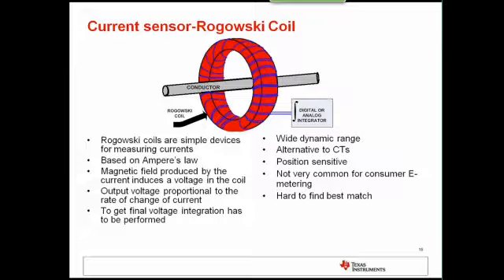This slide shows the third type of current sensor, Rogowski coils. They are simple devices for measuring currents based on Ampere's law. A magnetic field is produced by the current flowing through the conductor, causing an output voltage proportional to the rate of change of current. This has to be integrated, so one disadvantage is you either need external circuitry for analog integration or do it in software using the CPU. Another disadvantage is that it's position sensitive, and it's hard to find the best match.